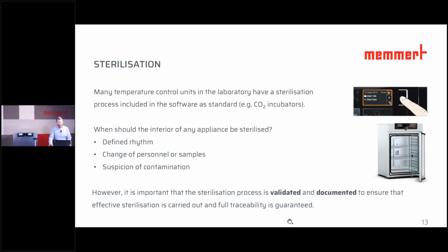This question is difficult to answer and depends on various factors. Basically, you can say the interval should be fixed by your own SOPs. However, a change in personnel or sample is always a good time to start a sterilization routine. Of course, the interior should always be sterilized as soon as contamination is suspected. Please note, a sterilization process must always be validated and documented.